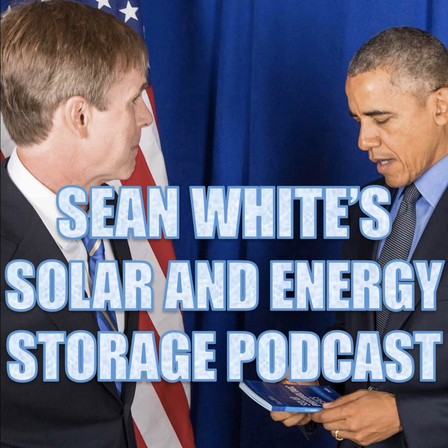Since PV prices are getting so low, at this rate, they will pay us to take it in a few more code cycles, so why not save money on smaller wire? If you do not see Bill's name on the next edition of this book, it means the copper industry has taken him out for reducing the amount of copper required on a PV system. Sean hears that overcurrent protection device manufacturers also have put a hit on him. It is dangerous writing the National Electrical Code.